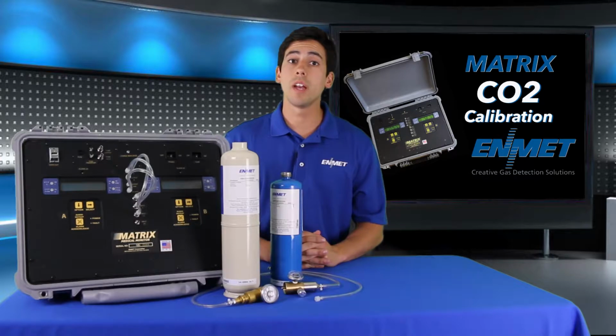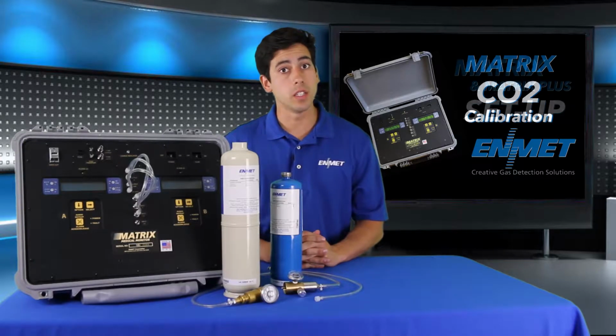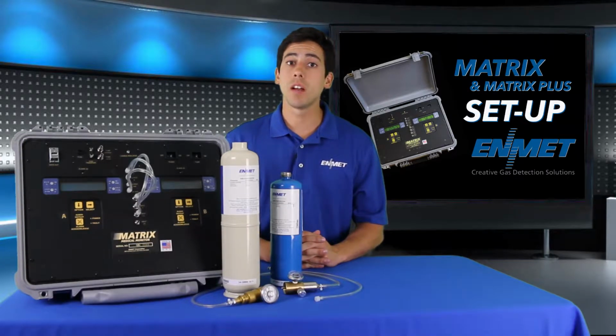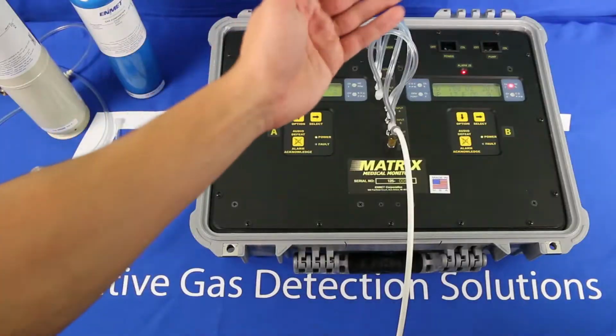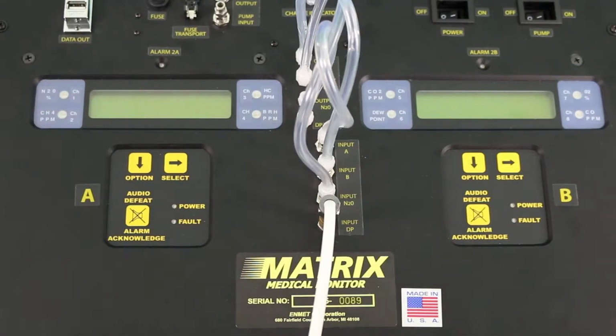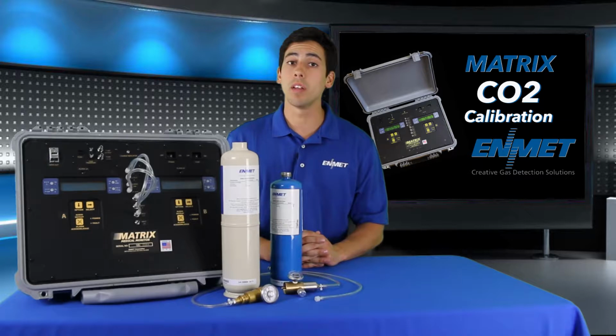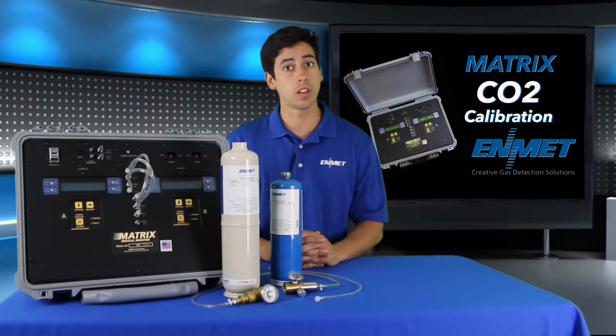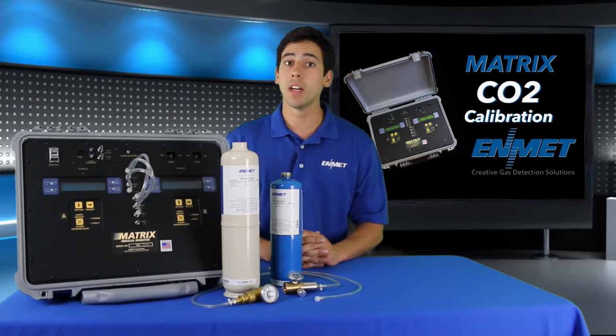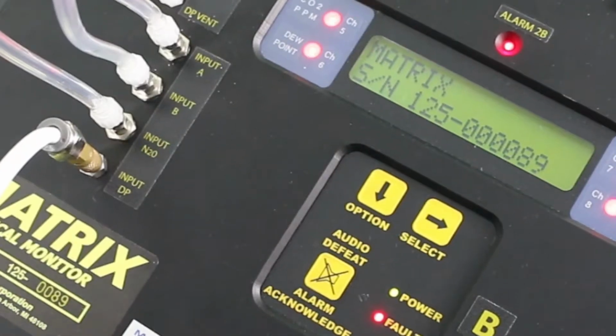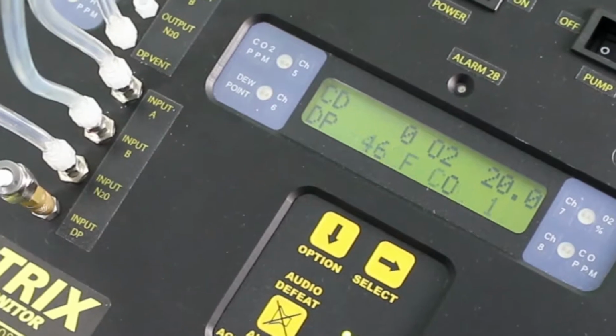If you need help with setting up your matrix for calibration, please see our matrix setup video. Here, we have a properly set up matrix unit that we are going to calibrate the carbon dioxide sensor with. The carbon dioxide, or CO2 channel, for this model is located on the right display screen.